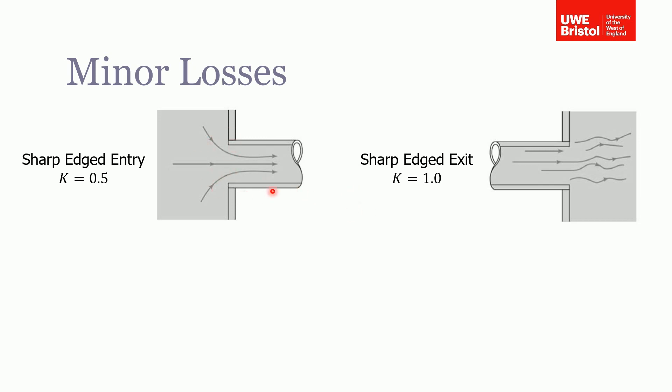So here's an example of a sharp edge entry, going from a tank entering the pipe, so the loss coefficient for this is 0.5, and here we have a sharp edged exit where the loss factor is 1.